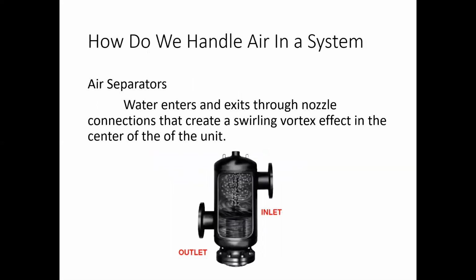The first item we'll talk about is air separators. An air separator is the way for us to eliminate air. Water comes in through each inlet and goes through a very tight channel or nozzle, and the connections create a swirling vortex effect in the center of the unit.